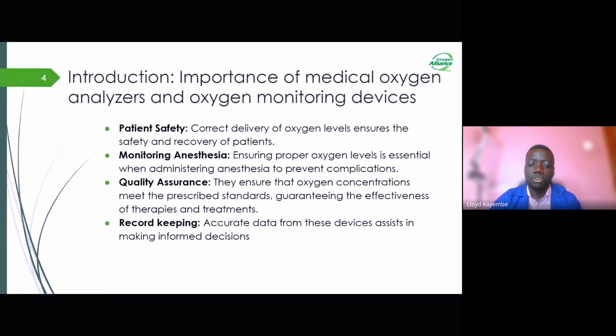Oxygen analyzers will help ensure that the machine or the source of the oxygen that you have is meeting the specified standards, so as to ensure the effectiveness of oxygen therapy and treatments. Oxygen analyzers will also help to assess if oxygen concentrators are working in the right condition. Oxygen analyzers also help in record keeping.